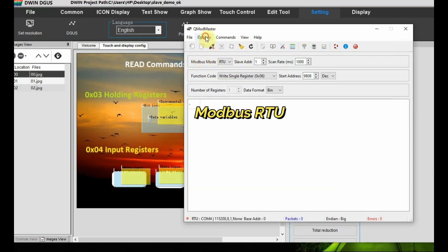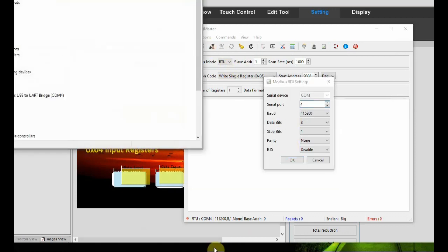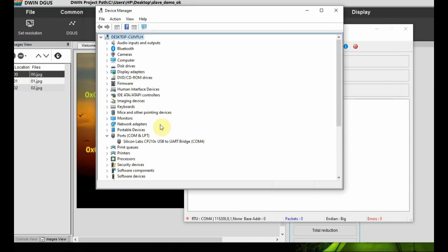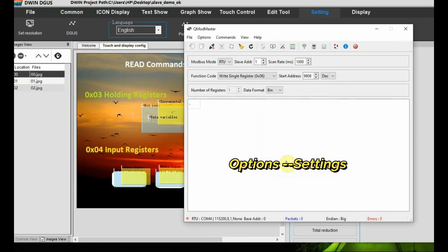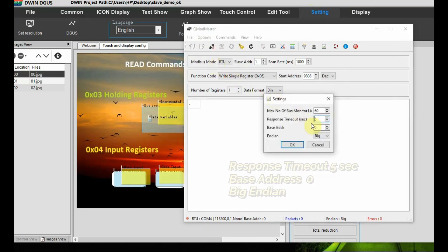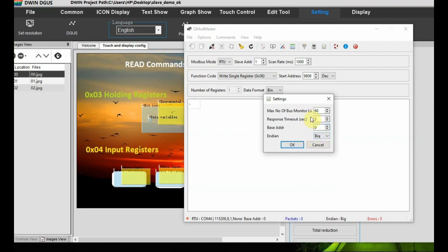In the settings, from Options click on Modbus RTU and then configure the communication settings. Select the serial port - we have used RS485 to USB and the COM port is allotted there. Baud rate is 115200 as the OS file we used is 115200, and settings are 8 and 1. From Options Settings select the response timeout - provide five seconds. Base address is zero, which is very important, and endian is Big Endian.